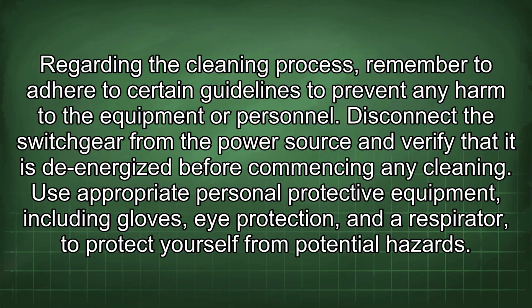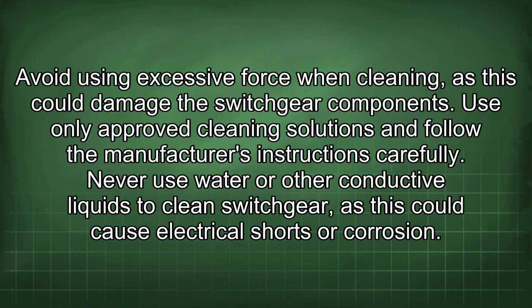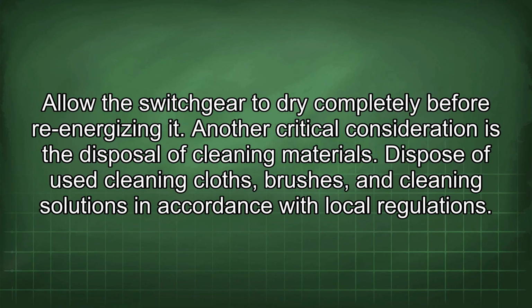Disconnect the switchgear from the power source and verify that it is de-energized before commencing any cleaning. Use appropriate personal protective equipment, including gloves, eye protection, and a respirator, to protect yourself from potential hazards. Avoid using excessive force when cleaning, as this could damage the switchgear components. Use only approved cleaning solutions and follow the manufacturer's instructions carefully. Never use water or other conductive liquids to clean switchgear, as this could cause electrical shorts or corrosion. Allow the switchgear to dry completely before re-energizing it.